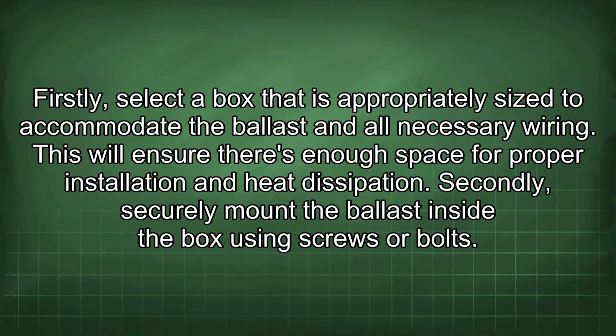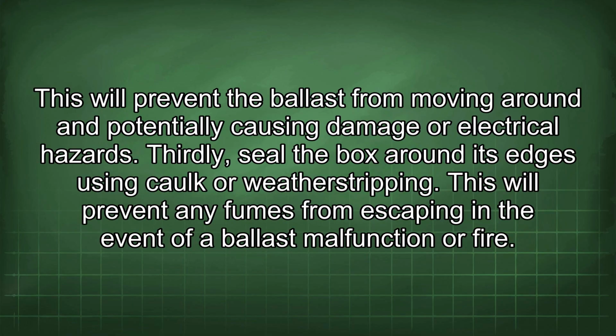Secondly, securely mount the ballast inside the box using screws or bolts. This will prevent the ballast from moving around and potentially causing damage or electrical hazards. Thirdly, seal the box around its edges using caulk or weather stripping. This will prevent any fumes from escaping in the event of a ballast malfunction or fire.